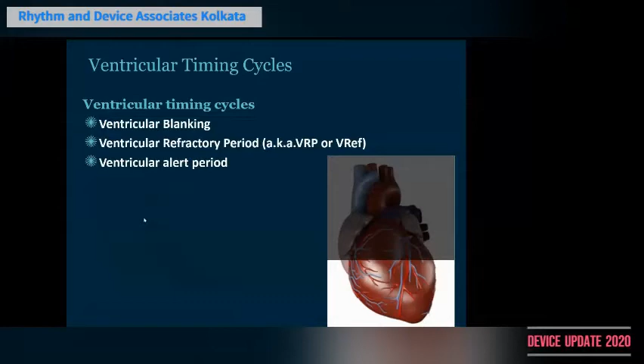So what are the ventricular timing cycles? Ventricular blanking: after the ventricular pacing spike is given or a ventricular sensed event is detected, a ventricular blanking period starts when nothing is detected and nothing is recorded. After that, there is a refractory period where things are detected, although these are not used for resetting the ventricular timing cycle intervals. So you have a blanking period and you have a refractory period. The rest of it is basically the ventricular alert period.